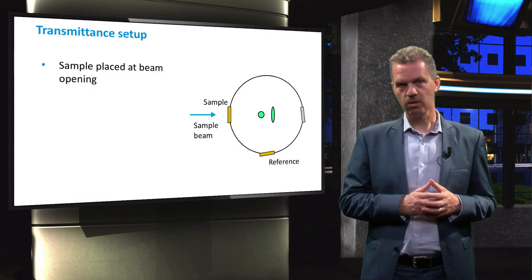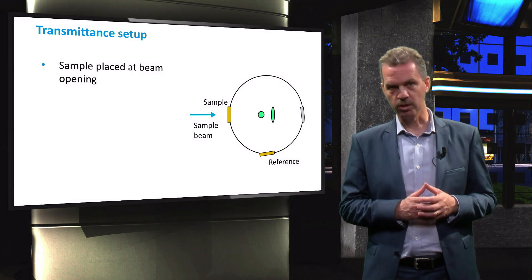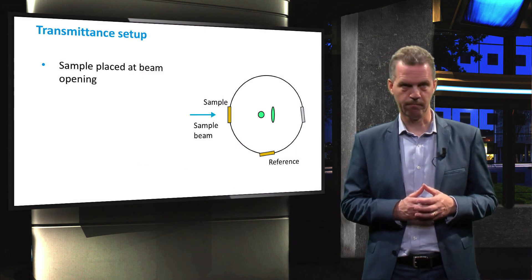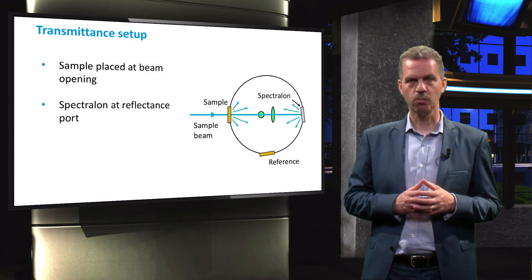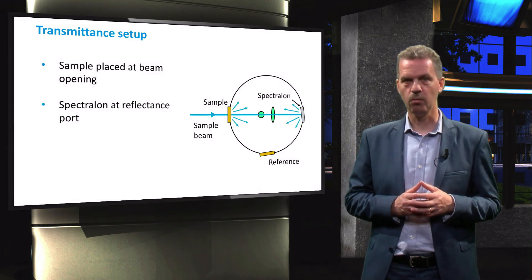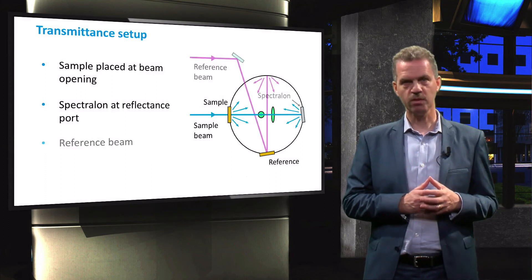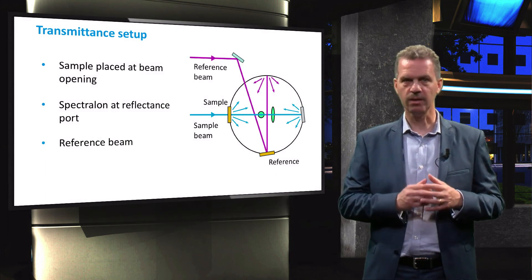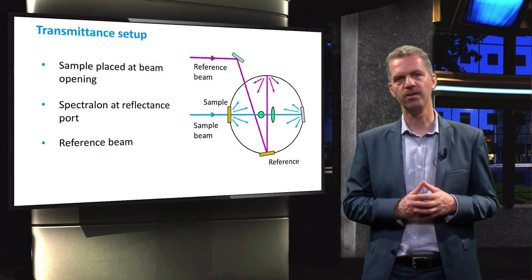When the transmission of a solar cell or material is measured, the sample is placed at the beam opening. The opening for the reflectance measurement will be closed with spectralon. Again, a reference beam is directed into the integrating sphere to correct for the reflectance of the spectralon in the chamber.